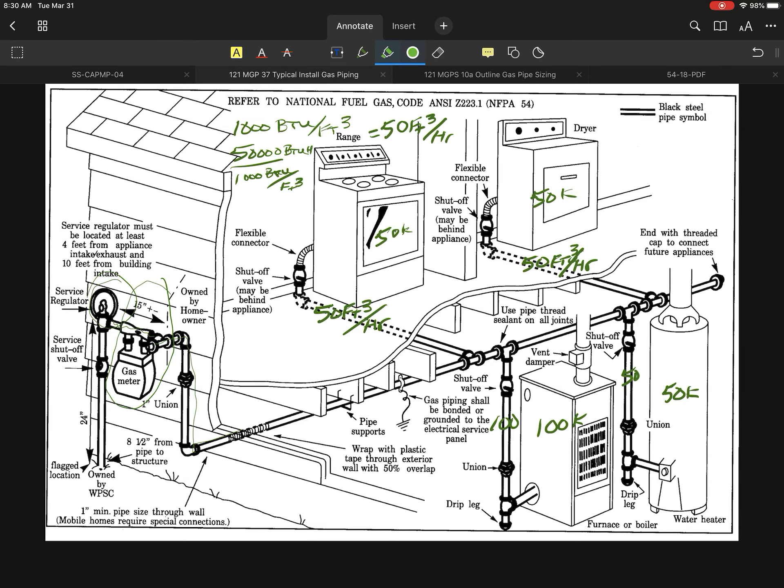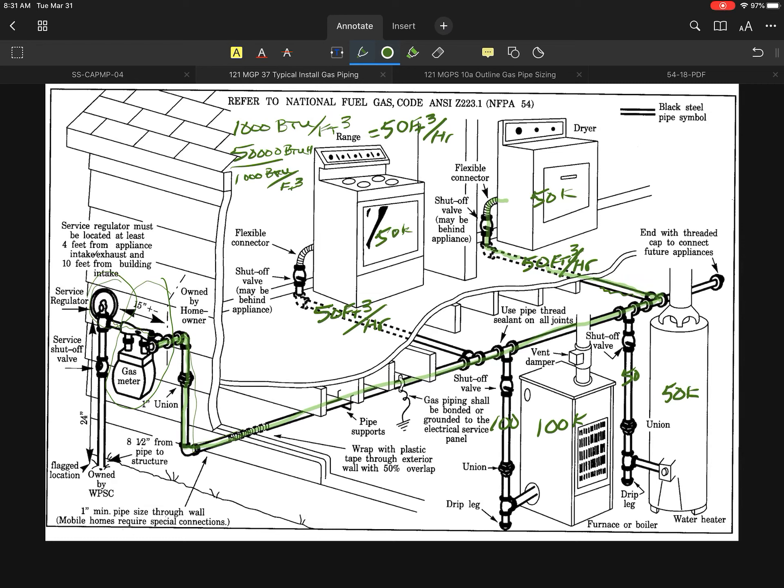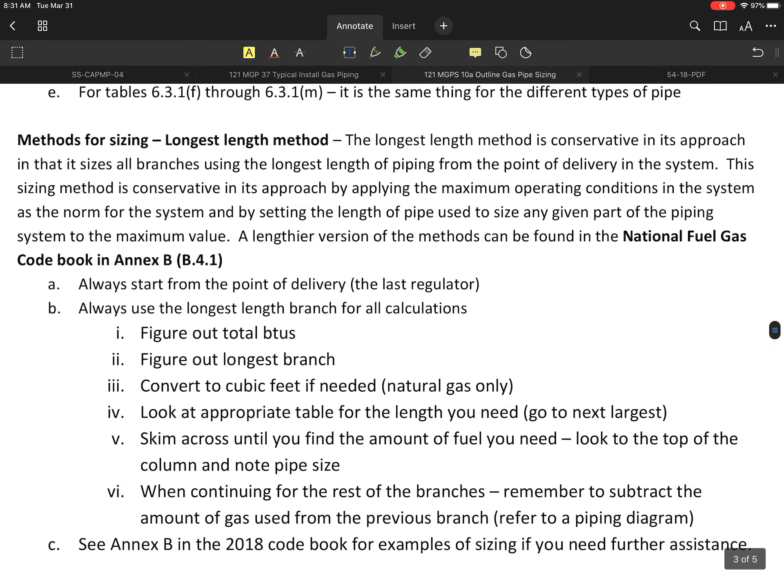When I look at my piping system, it seems fairly obvious by the picture, disregarding any lengths or anything like that, that my longest run would run this whole length. Let's say we go to the very last one and I'll call this one my longest run from the whole distance of this branch plus the main. Let's say that run happens to be 76 feet in total.